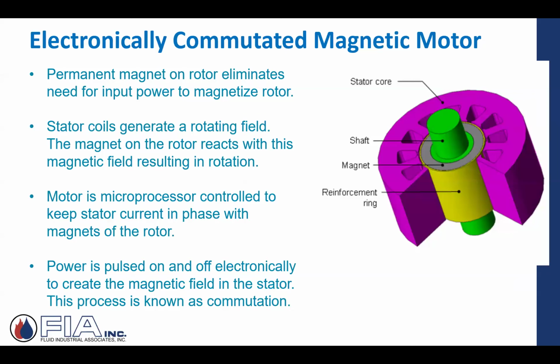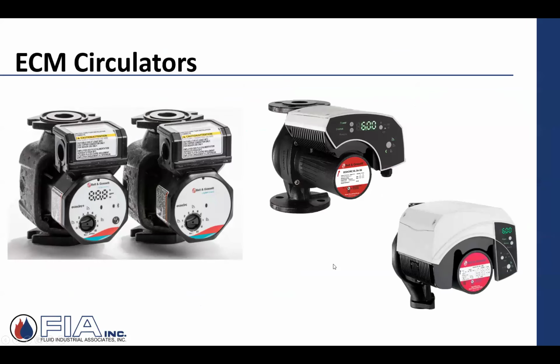ECM, very easy to say, stands for electronically commutated magnetic motor, which is why we stay with ECM. It's a lot easier to pronounce. What they're referring to is they install magnets on the rotor, which is part of creating that magnetic field. Another thing that's very different, and sometimes you'll hear the expression when you talk ECM, is people might say, hey, that's a smart pump. You get smart pump technology.